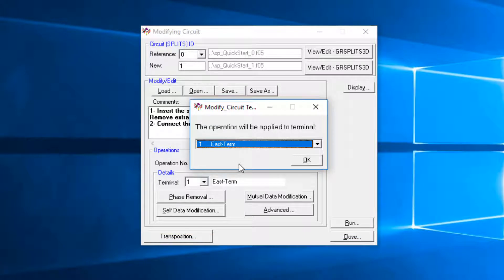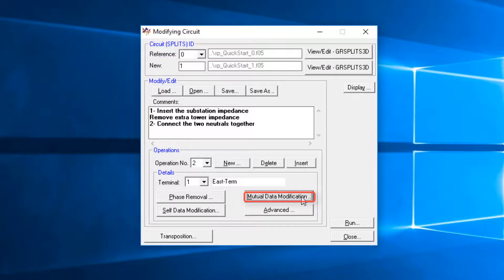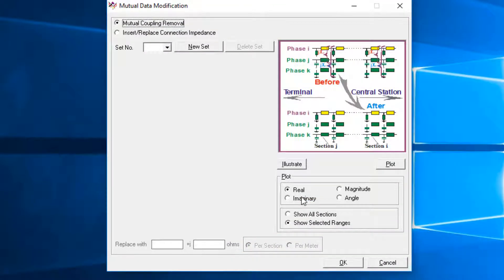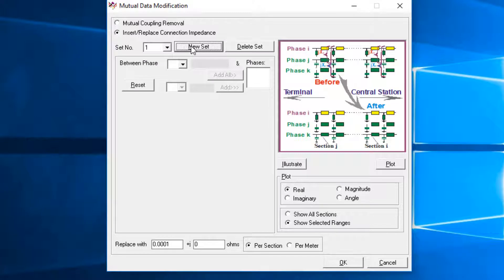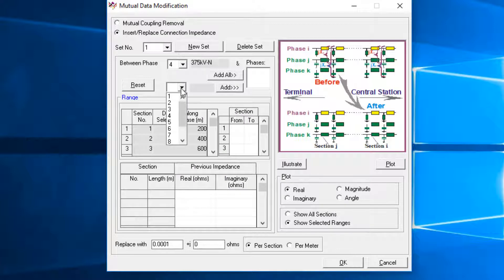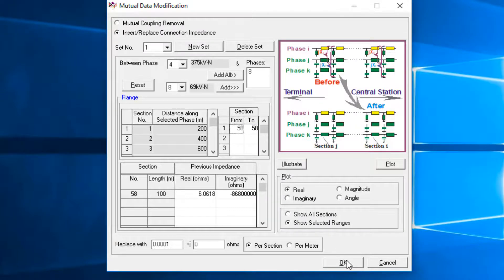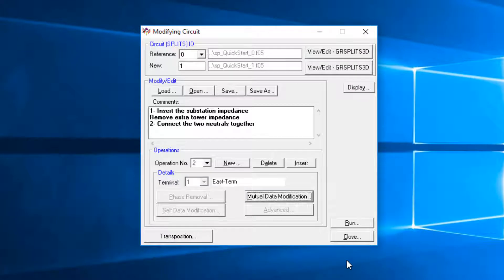Click the New button to start another operation, but this time click on the Mutual Data Modification. Operation 2 is defined by using the Insert-Replace Connection Impedance Width option. Click on the New Set button. Select between Phase 4 and 8, Enter from Section 58 to 58. This will connect these two phases at the substation location, where they both connect to the grounding grid.